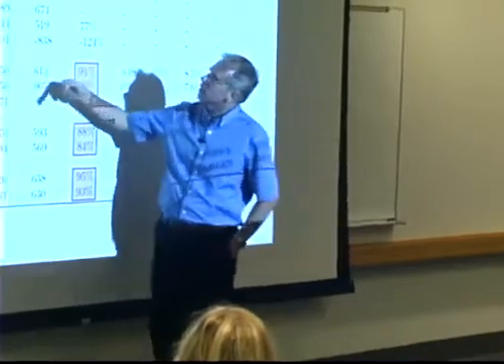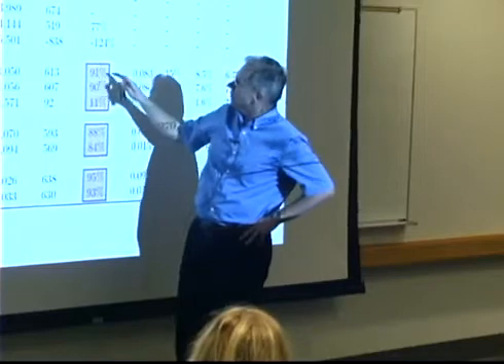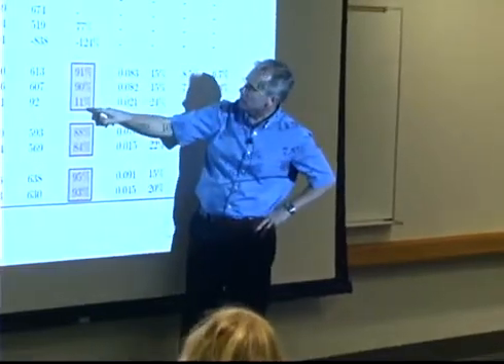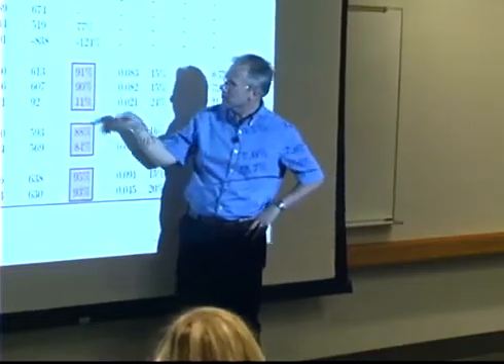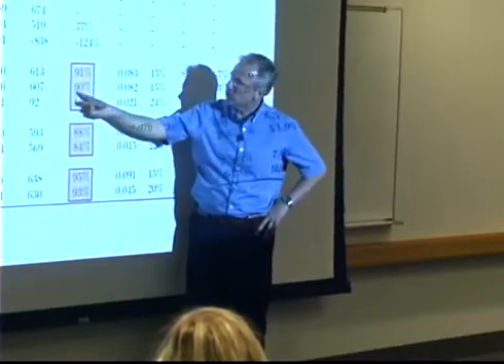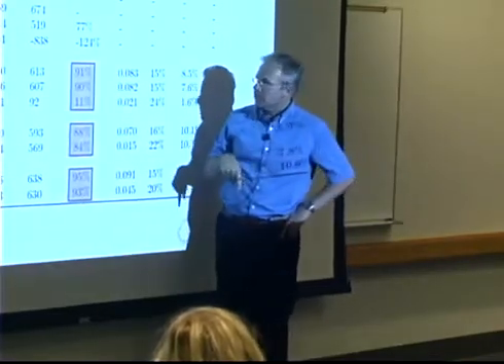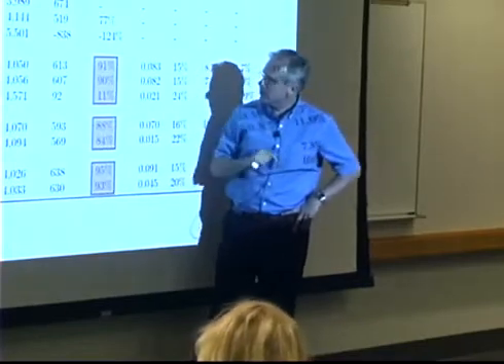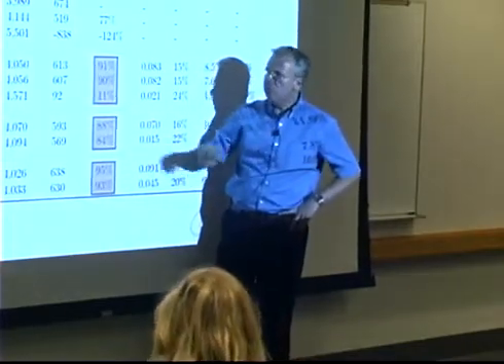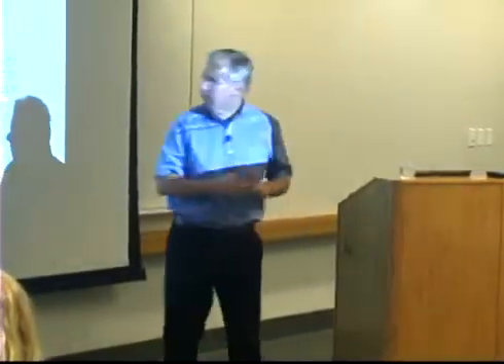So the optimal savings are shown here. Savings, yeah, this is savings. And of that savings, in the open loop design, in the open loop test, we saved 91 or 90%. That looks very promising, but we realized that as soon as we took the rules and applied them in closed loop fashion, we only achieved 11%. So the rule really breaks down once we put it into place. Whereas for the CART, we looked at several CART models, and that second CART model was showing 88% of the optimal result in an open loop and 84% in a closed loop fashion, which means that of the optimal result that I get from an offline simulation or optimization, I can maintain about 80% and implement that as a rule.